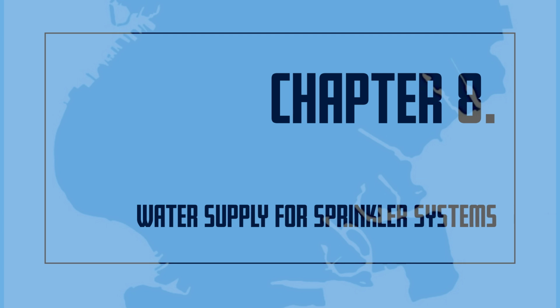However, a single supply may be out of service for maintenance or repair during a fire emergency, or it may be disabled during a fire or before the fire is fully extinguished. Additionally, the water supply may fall below normal pressure or volume during an emergency. These are just a few reasons why it is good to have a secondary water supply. In some cases, it is required by law to have a secondary water supply source. Whether a second source is needed depends on several factors. These factors include the strength and reliability of the primary supply, the value of the property, the height, area, occupancy classification, and design of the building.